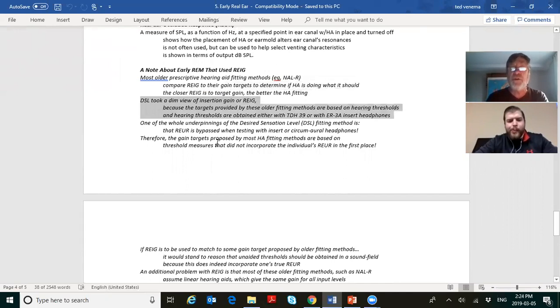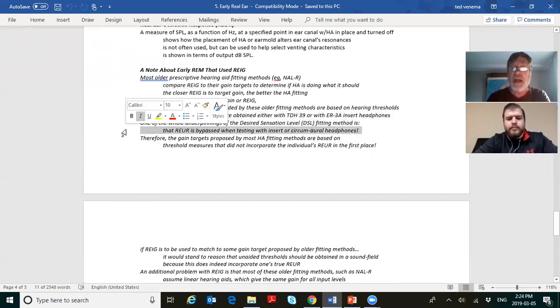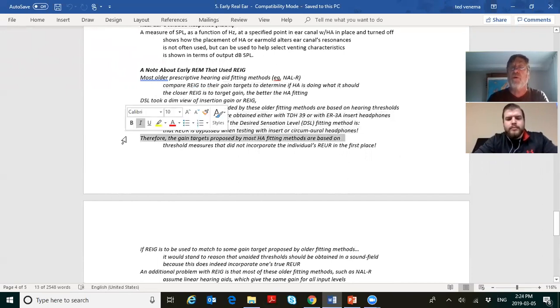DSL took a dim view of insertion gain because the targets provided by the older fitting methods are based on thresholds, and hearing thresholds are obtained with circumaural or insert headphones. One of the whole underpinnings of the DSL fitting method is that real ear unaided response is bypassed when testing with headphones. Therefore, the gain targets proposed by most hearing aid fitting methods are based on threshold measures that did not incorporate the individual's unaided response in the first place.